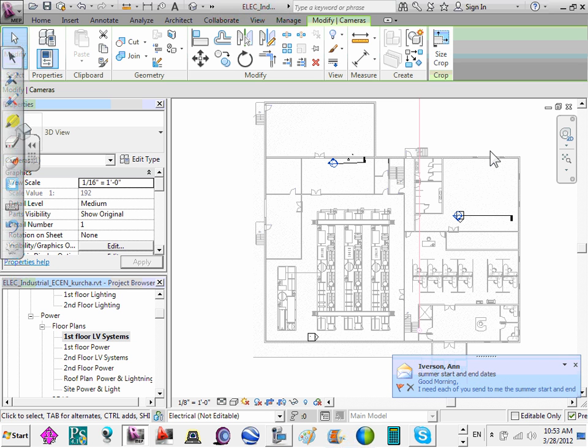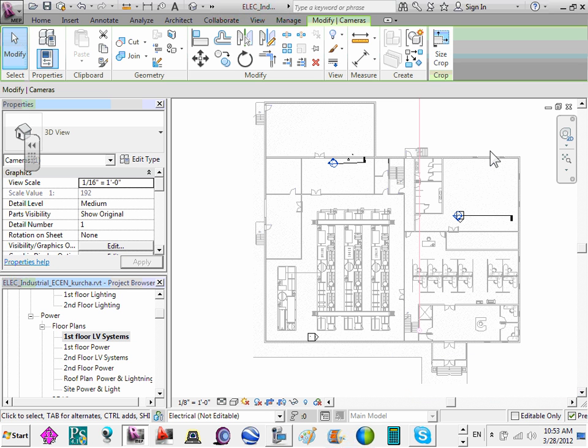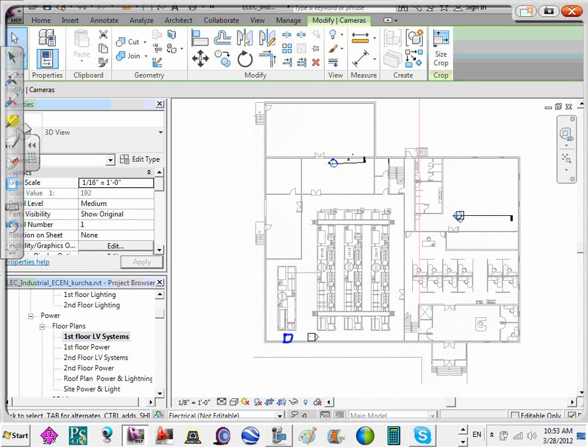So you're going to have roughly 50 feet on center. You go 50 feet here, and if you're 20 feet here, then you go up 30 feet this way, and all the way around. If there are poles in between, you can go in between, but I would just typically do the perimeter and flood this area with the horn strobes.